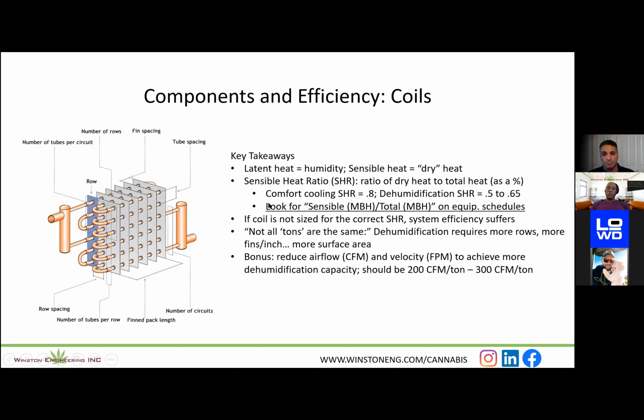So if you're looking at some design drawings and you want to know if your design is appropriate, a real easy way to look is to look at the equipment schedule. That's the portion of your drawings that tells you what equipment goes where. And more than likely, you'll see sensible MBH, and you'll see a total MBH. Divide the sensible by the total and see where your sensible heat ratio is. If you're at a 0.8, you might want to ask the question. If you're at a 0.5, you're probably all right.